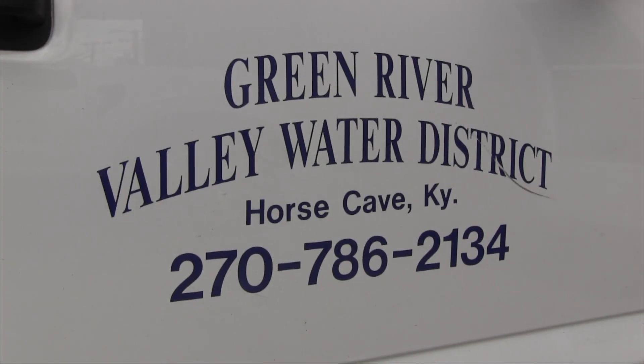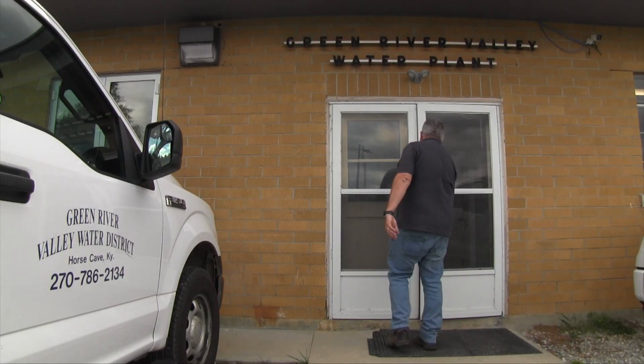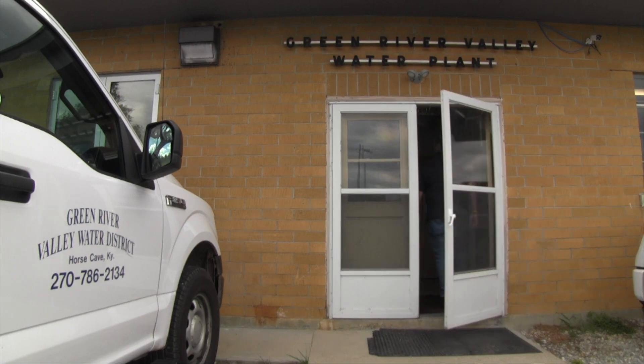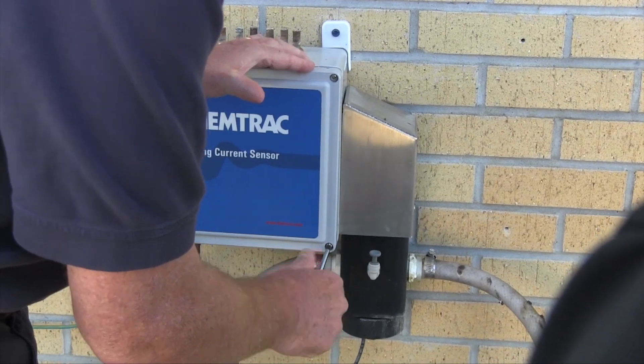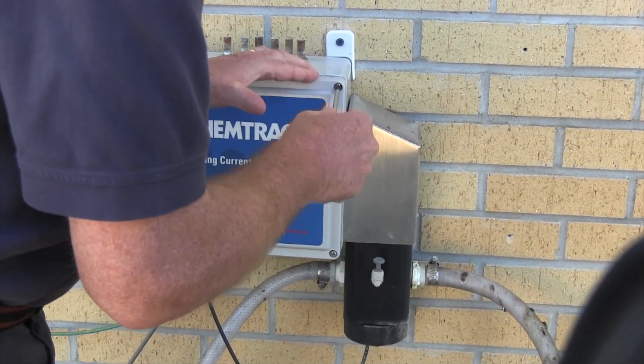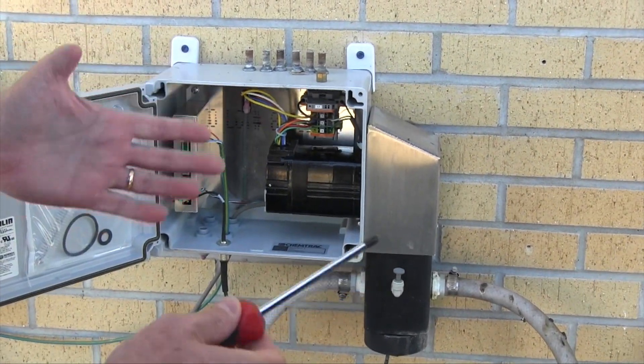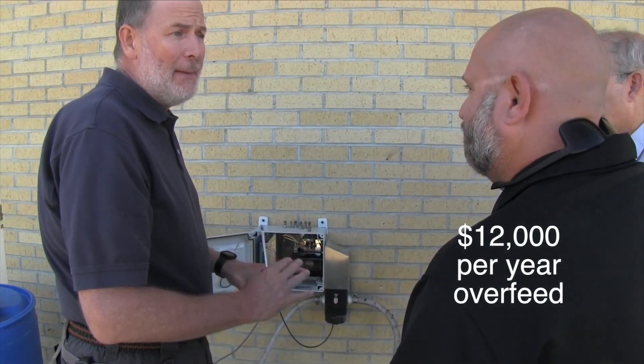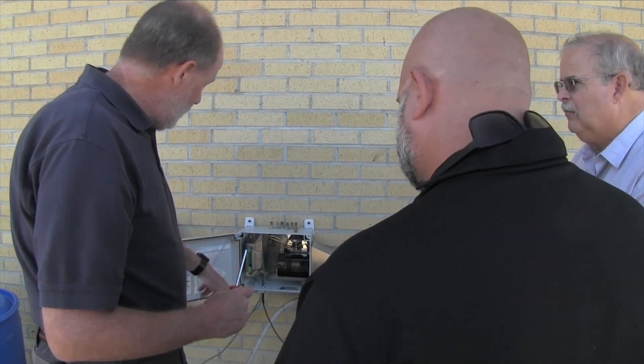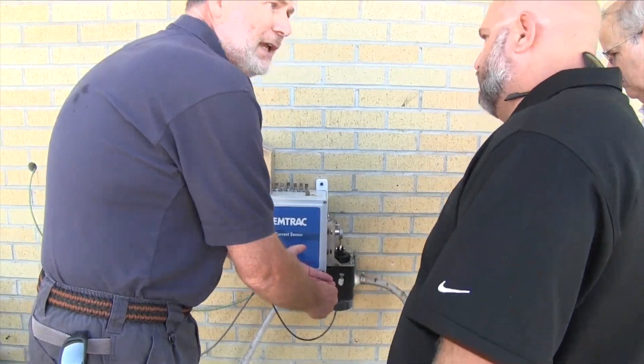I've been here for seven months now. In the past I've used a streaming current monitor, and I wanted to use that technology here. The first week I was here is when I reached out to get a ChemTrac. Got approved no problem once I showed them the financials of how much we were overfeeding. When you're throwing away $12,000 a year because you're overfeeding a chemical, it's common sense — you've got to optimize in every way you possibly can. Within one week we were already going in a different direction.